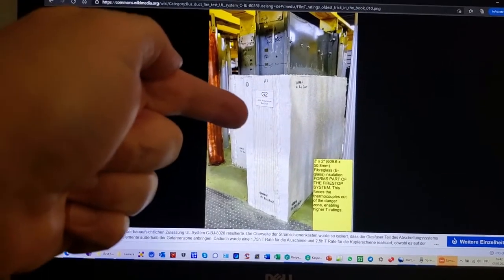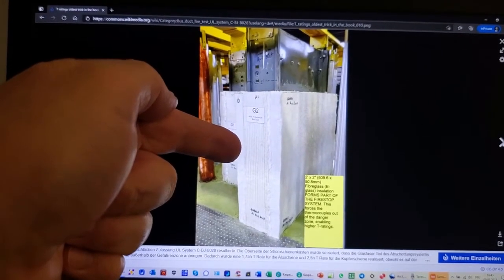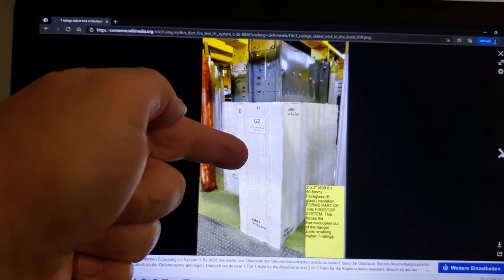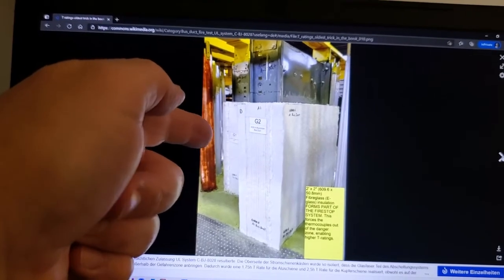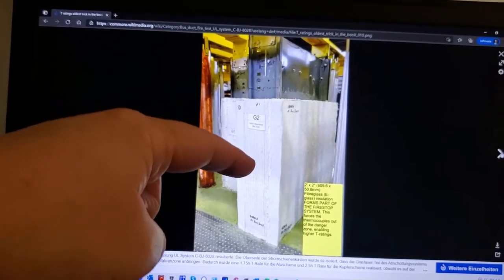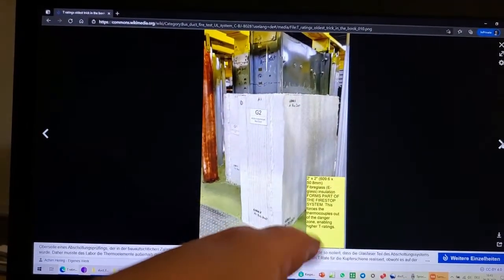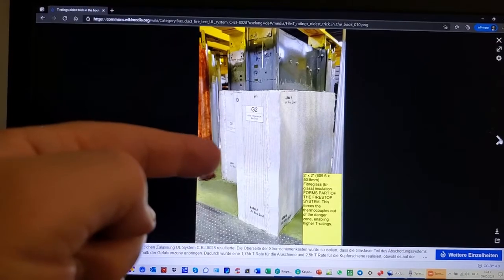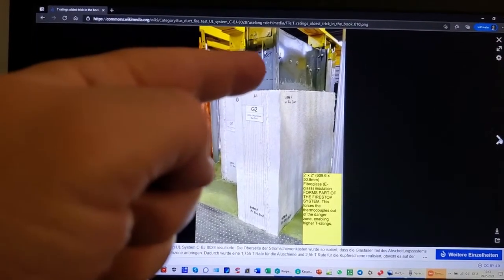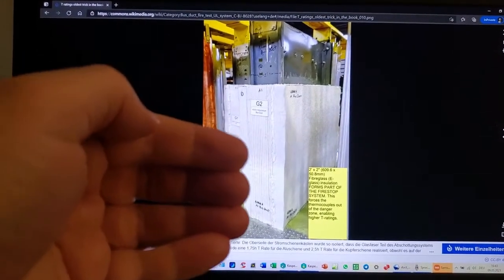So it's a way of circumventing the system, and this, in essence, is the oldest trick in the book. And this exactly is what folks are using to get into the alternative path of approvals for pressurization ductwork according to the International Building Code. Because what they're doing is using this particular old fire stop trick to deliver thermal data that can be misconstrued by some folks to think that, oh, the inside of the duct is safe, therefore the fan is safe, right? Obviously, this is a bus duct, it doesn't have a fan on the inside. But I'm making that comparison.